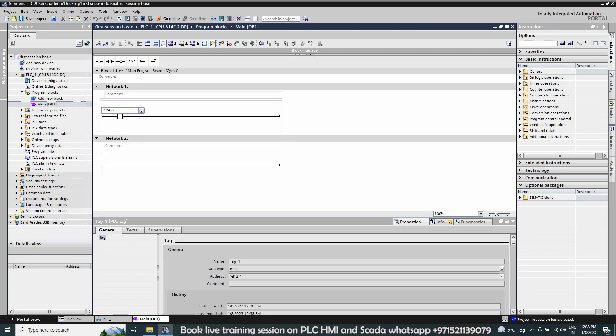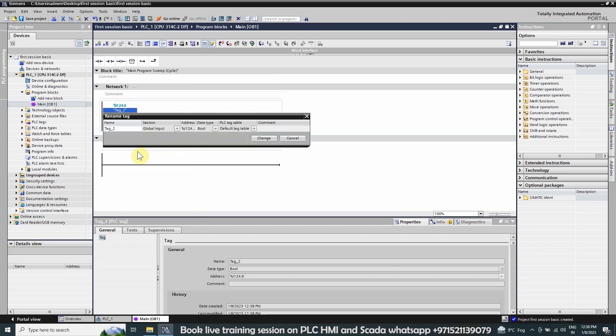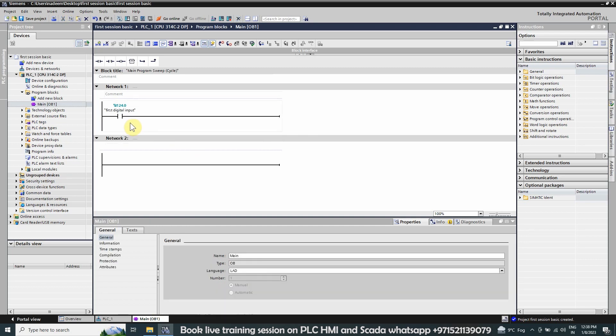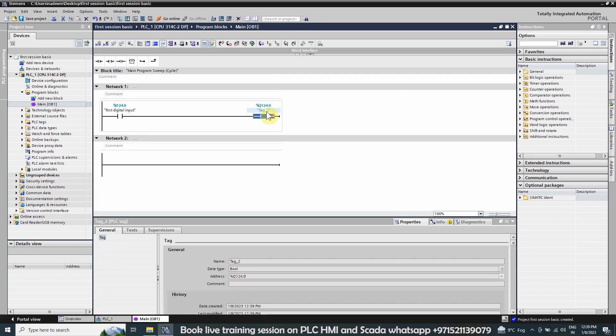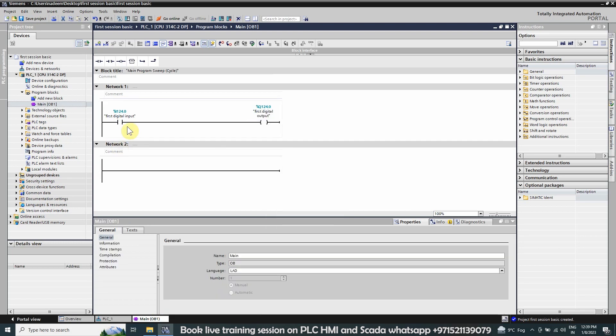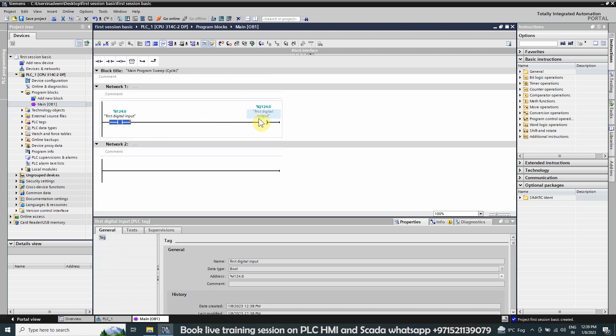We assign the address I124.0, which is our first digital input, and change the tag name to 'First Input'. Next we add an output coil with address Q124.0, which is our first digital output, and rename its tag accordingly. We have created a simple ladder: whenever the first digital input is on, it should turn on the output coil Q124.0.